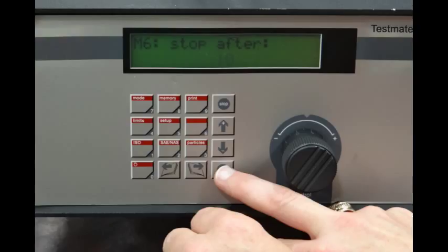This means that the TPM will take 10 different samples of the fluid in the reservoir and give you a reading that is an averaging of these readings.